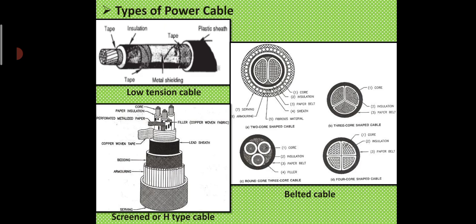This is because tensile stresses are produced in paper insulation due to the dielectric field at high voltage. Now, the strength of the belt insulation is less in tangential directions compared to that in the radial directions. Moreover, the dielectric loss does not remain uniform. As a result, voids and wrinkles are produced in the paper due to its more thickness, which is not desirable for the insulation.